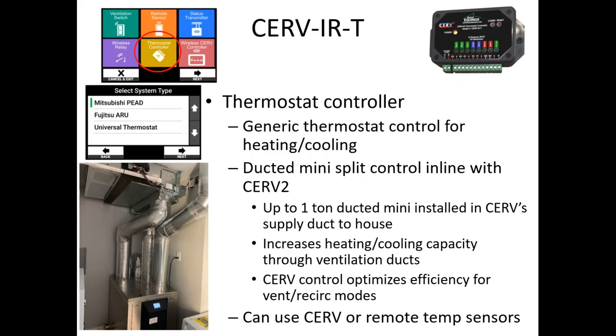CERV IR is something new. This is what we've written about in our Magic Box Mechanical Room articles. This is integrating the CERV with a ducted mini split. So this controller is what controls the mini split. It can be set as a generic, universal thermostat to control heating or cooling systems, or specifically you can select certain brands of ducted mini splits, and that gives the CERV control over that system. And we work with them here at our facility to optimize that operation.